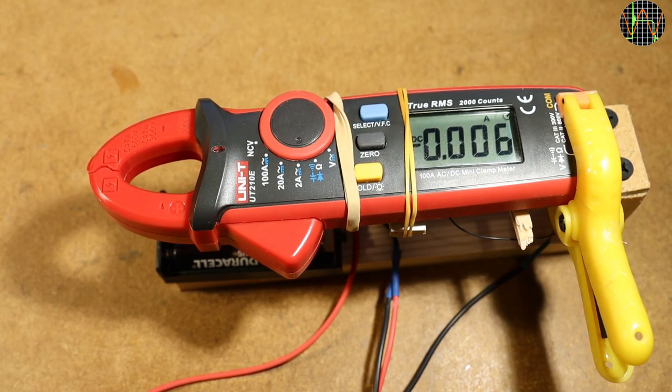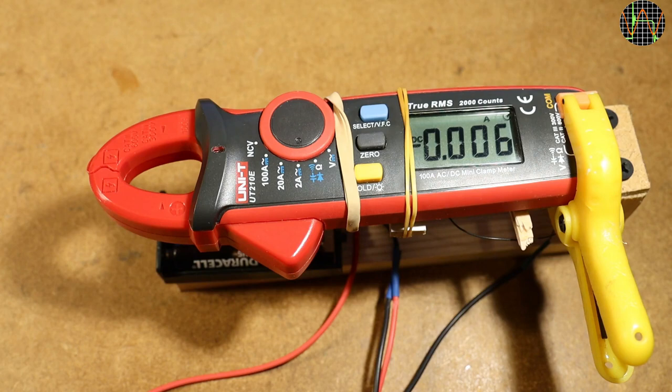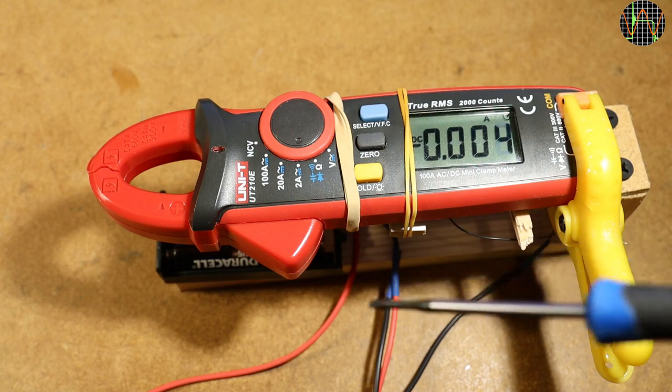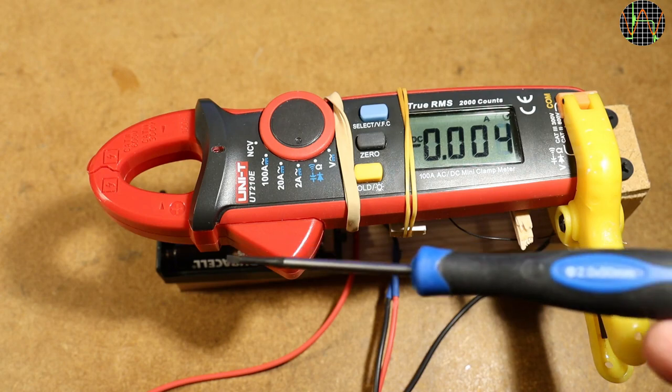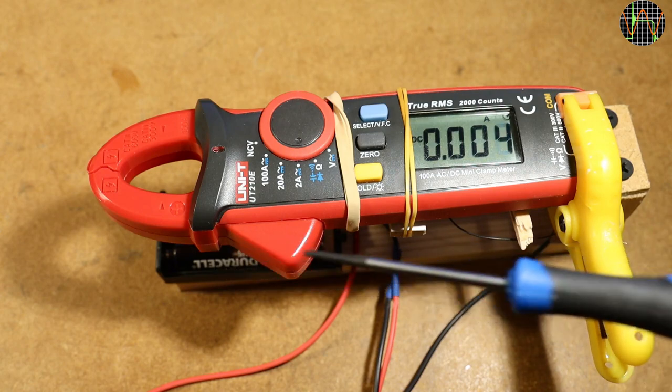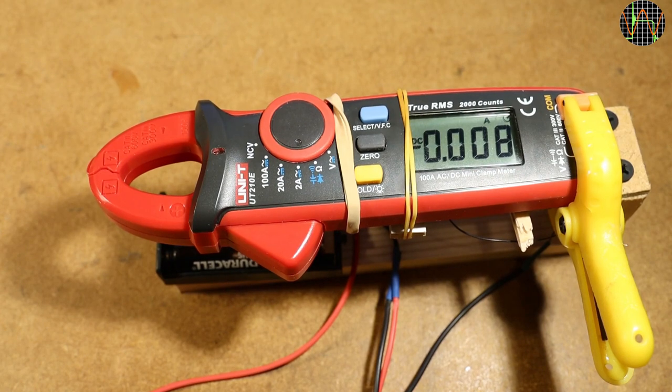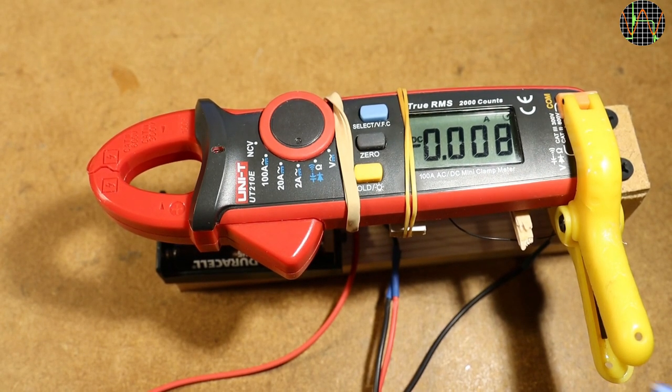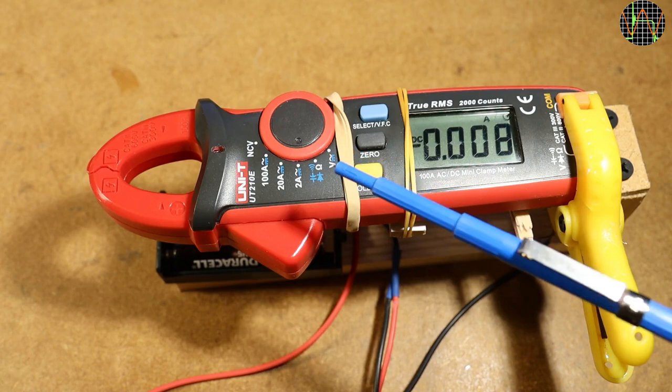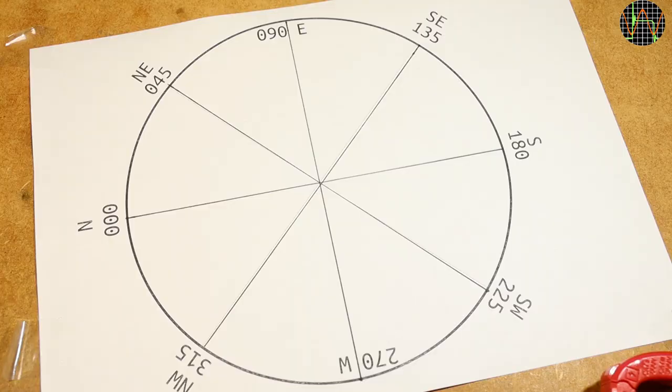Firstly, no magnets must be anywhere in the area where the alignment is taking place. Here I am moving a reasonably strong neodymium magnet half a meter distance away and the meter still picks up that field. The same is true for the tool that you use to adjust the trimmers. It must not be magnetic. If necessary, demagnetize it until the meter shows no effect if you bring it close. There are special tools for adjusting trim pots but even these should be checked.